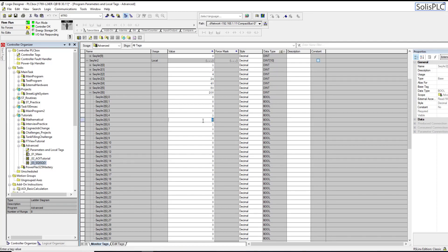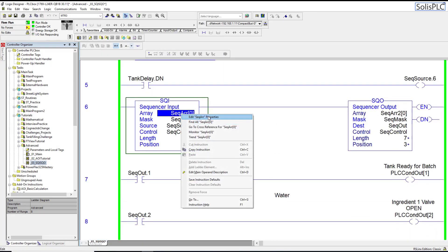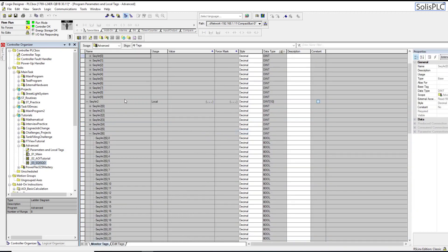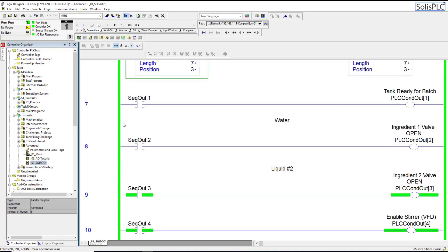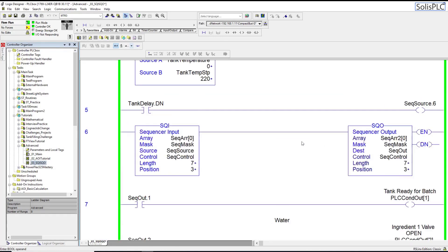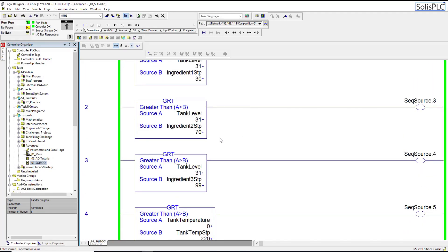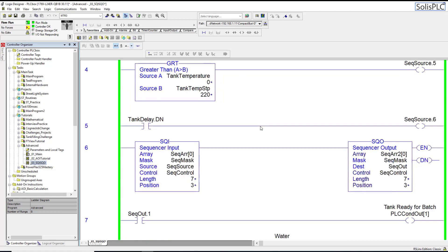We also need to go back to the input array because I've only specified a couple of them. There's going to be values one, two, four, eight, 16, 32, 64, 128 - let's step through this. Since we are feeding ingredient number two and stirring, this means we are waiting for input of sequence number three, which needs to be 71 or above. Once we reach that level we can step through.